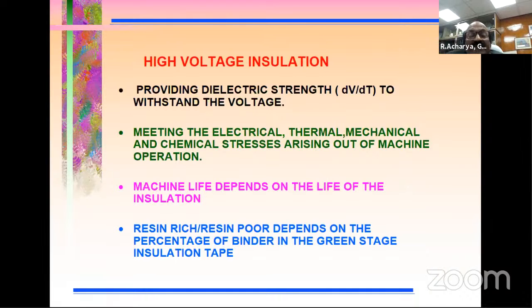There are machines also operating at 27 kV terminal voltage. From that backdrop, you can see that the basic objective of insulation is to provide the required dielectric strength - what you have studied as dV by dt, the voltage withstandability with regard to thickness to withstand the voltage. The second thing is that insulation is not just for electrical purpose; it has to meet the electrical, thermal, mechanical, chemical, and all the stresses arising from machine operations combined. The machine life depends on the life of the insulation system, which requires refurbishment or maybe scrapping, whatever it is.